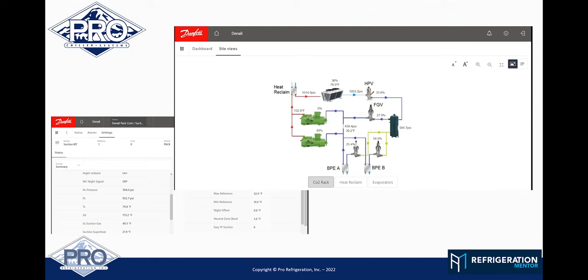You know, if you can take and go back, like say 2 weeks, and look at your flash gas valve. And with this system being a flash gas bypass system, what that flash gas valve's doing and what's happening in that flash tank tells you so much about the health of the system. So those are a couple points that a person could really dial into and look at and say, huh, why is my flash gas valve at 100% all the time? Why isn't it closing off? What's going on? Why is my flash tank at 600 instead of 550?